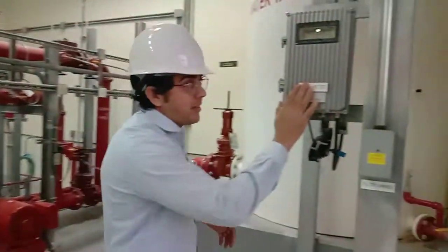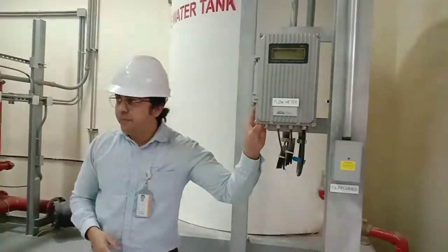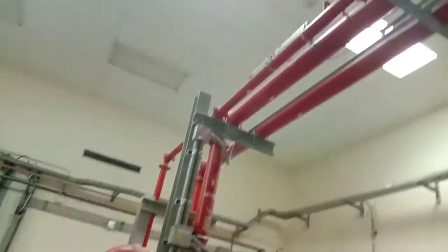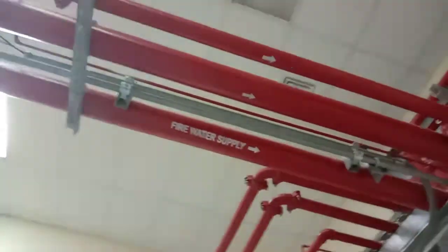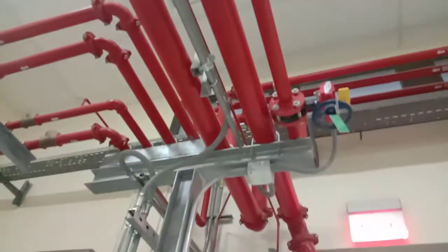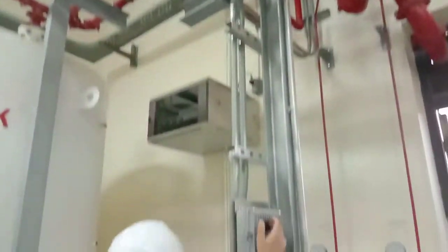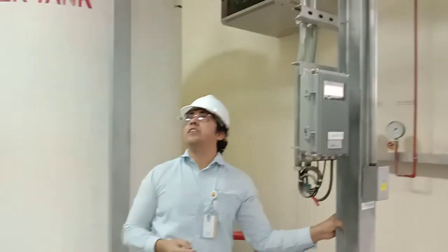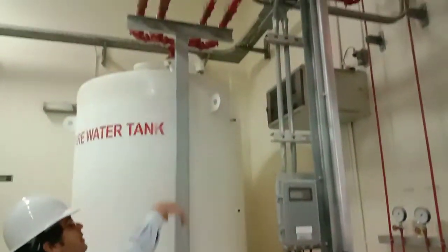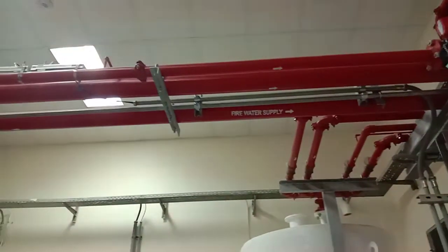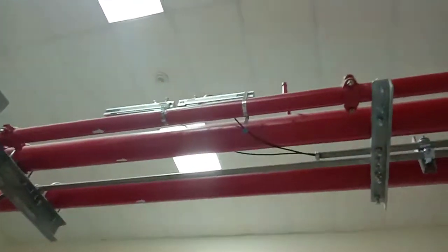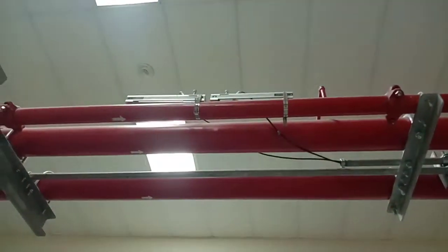So we have a flow meter arrangement, the second one from NFPA. Now this flow meter arrangement is the second one from the discharge side. This supply is going all the way back to the tank. You can see from here. So the idea of this one is, we open the valve for the testing, we measure the pressure at this location, and based on that we find the pressure and flow. And this line has a sensor, an electronic sensor connected at the top. You can see at this location here it is connected with the main pipeline. So those will go directly back to the tank.